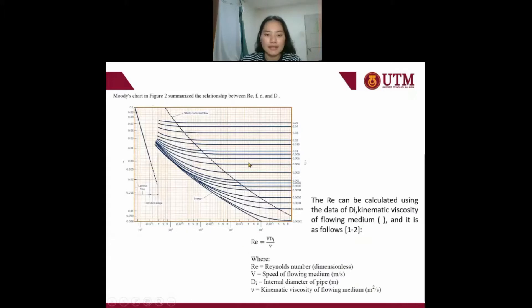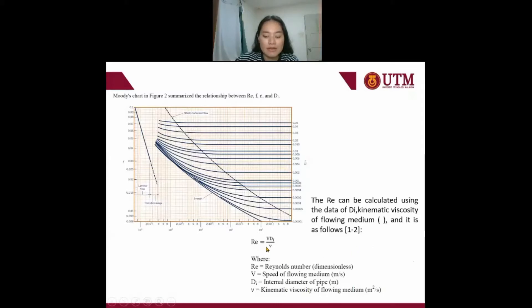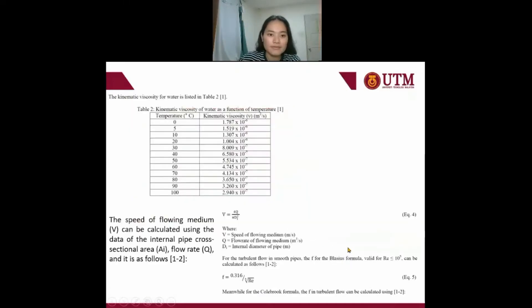This is the Moody chart. Here, the Reynolds number can be calculated using the data of internal diameter, kinematic viscosity of the flowing medium. The Reynolds number is equal to the speed of the flowing medium times the internal diameter, divided by the kinematic viscosity. This table shows the kinematic viscosity of the flowing medium as a function of temperature.